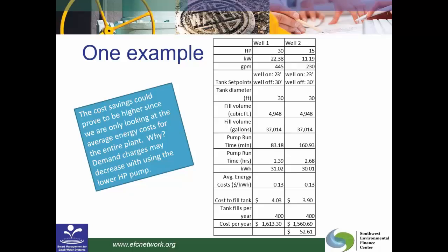But because well two is smaller horsepower, we end up using less energy to fill the tank with well two than with well one. And if we look at it over the course of a year, it costs us $4.03 to fill the tank with well one and $3.90 to fill the tank with well two. If we have 400 fills per year, the difference in the cost of running well two versus well one is $52. Does that mean we should never run well one? Well, probably not. Does that mean that we're saving a ton of money by running well two more often? Well, the $52 may not be the overall big picture, because we're using this average energy cost of 13 cents per kilowatt hour. It may actually save more than $52 a year because our demand charges may decrease when we're using the lower horsepower pump.